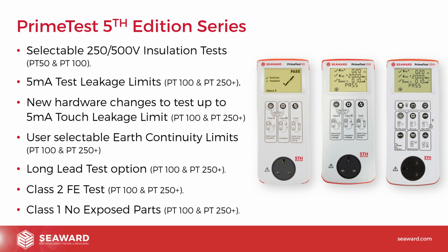Obviously, I mentioned earlier the 5 milliamp leakage test limits. The 5 milliamp leakage test limits are a 5th edition thing. It's been changed, and we've had to make changes to the firmware and the hardware within the products to allow them to measure the full 5 milliamp range. So a lot of other makes of PAT testers out there might not have made this change. So from Seaward's point of view, we're saying, to be fully 5th edition compliant, we've included this. If you've got an older tester, obviously you can still carry on using it. It'll just work to a lower pass-fail limit, whereas these will measure all the way up to 5 milliamps.